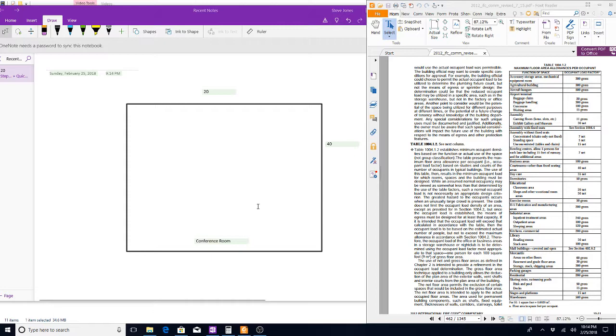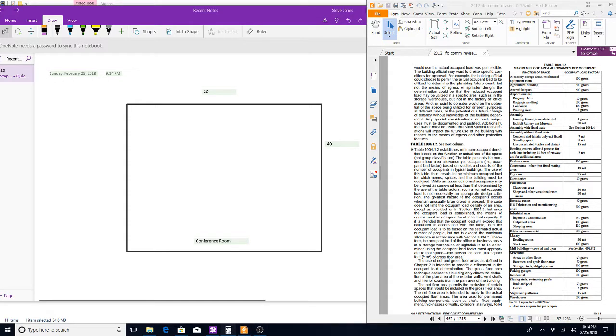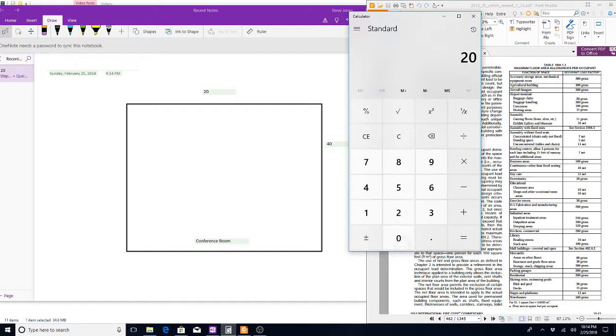In our example, we have a conference room that's 20 by 40. Looking at the table, we find assembly area with tables and chairs, which gives us a 15 net. So our occupant load factor is 15. To figure the occupant load, we take the square footage of the room — 20 by 40 — which is 800 square feet, and then we take the occupant load factor of 15 and divide by 15.